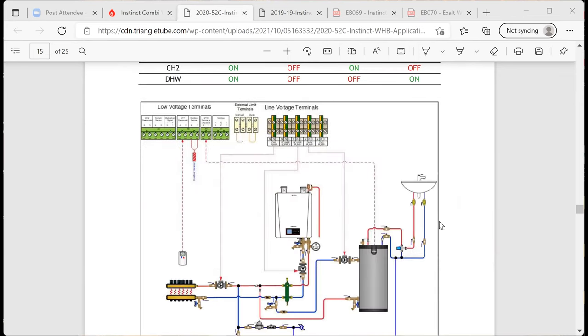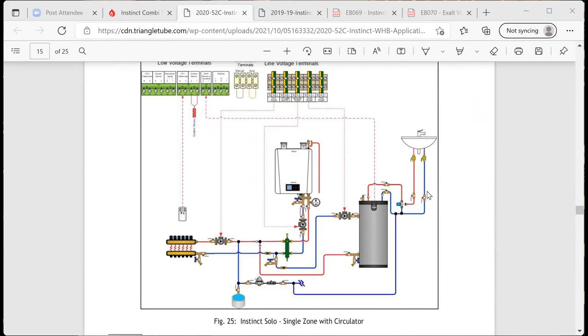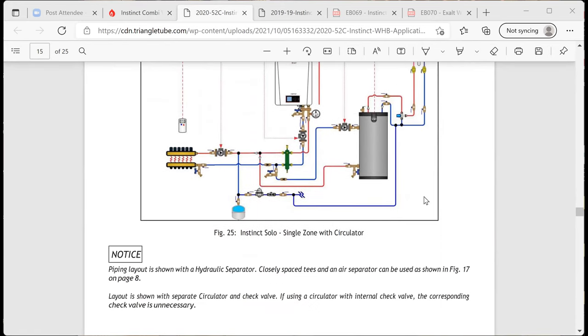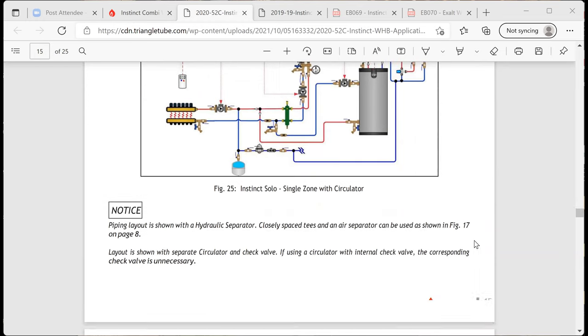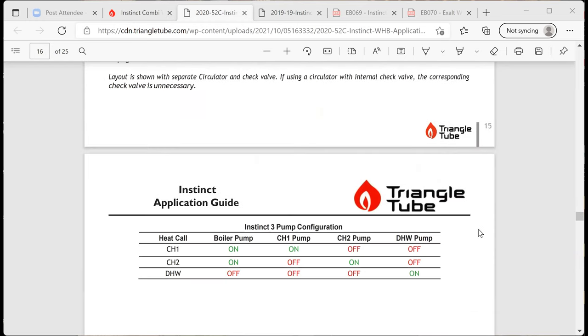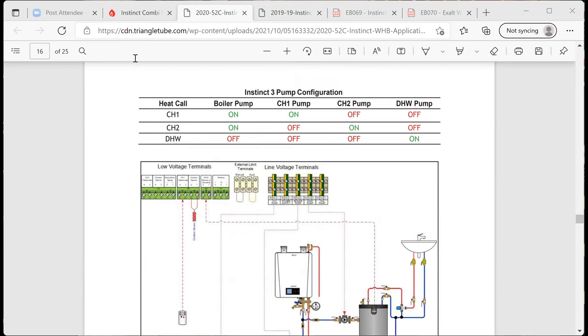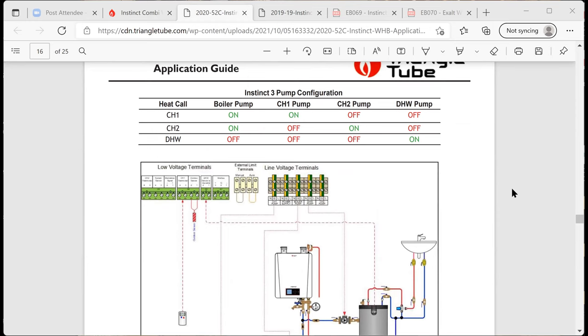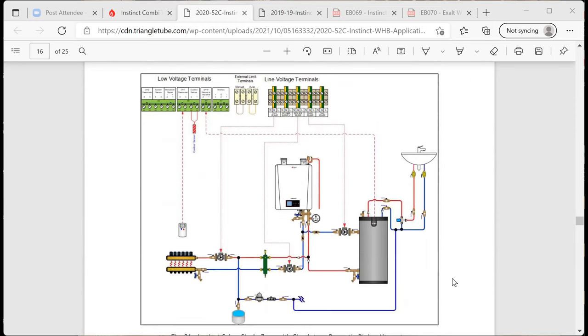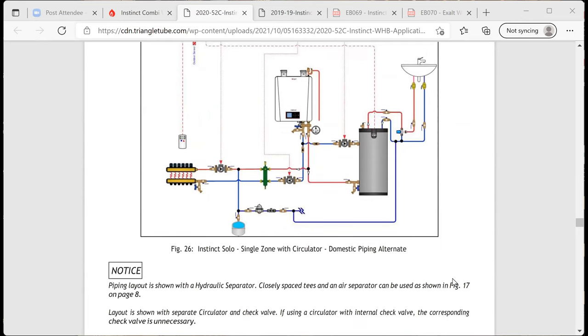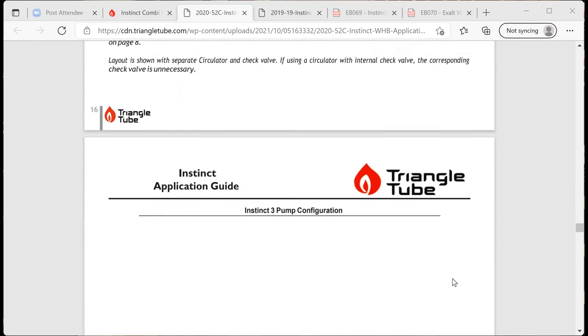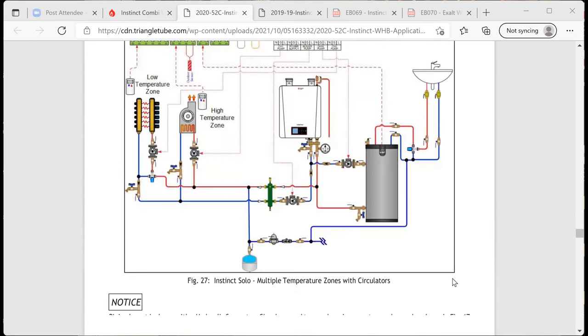So this application guide, they're great. I put a lot of information in here. Pretty much most of these piping diagrams are what most people are running into, but it also gives you your pump settings, what it recommends for your pumps depending on the installation. See if there's anything else down here that we need to go over.